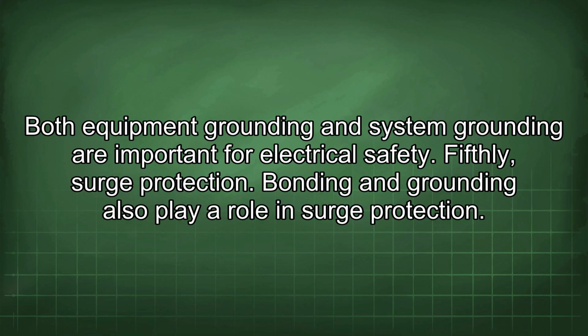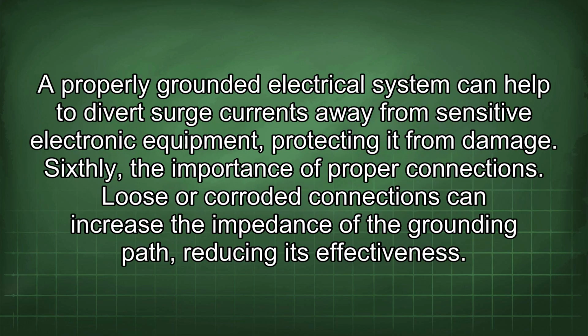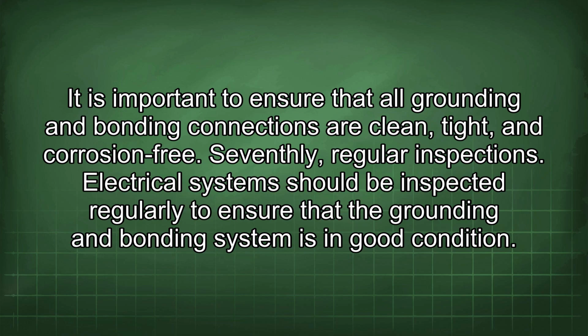Fifthly, surge protection. Bonding and grounding also play a role in surge protection. A properly grounded electrical system can help to divert surge currents away from sensitive electronic equipment, protecting it from damage. Sixthly, the importance of proper connections. Loose or corroded connections can increase the impedance of the grounding path, reducing its effectiveness. It is important to ensure that all grounding and bonding connections are clean, tight, and corrosion-free.